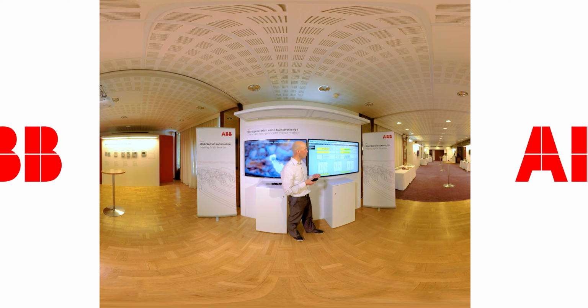You can see here that such a fault type as a restriking earth fault produces these current spikes. And through the Fourier transformation, we can see that each of these current spikes includes a lot of harmonic frequencies. So the frequency spectrum of each spike is quite broad.